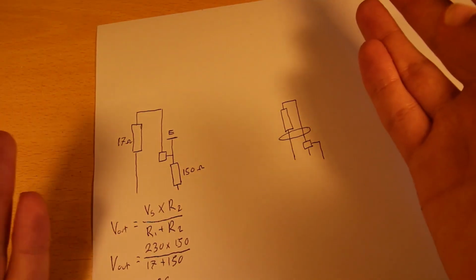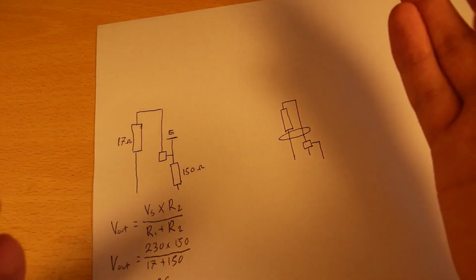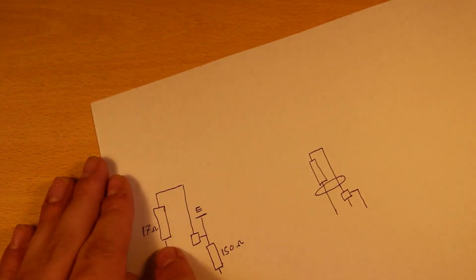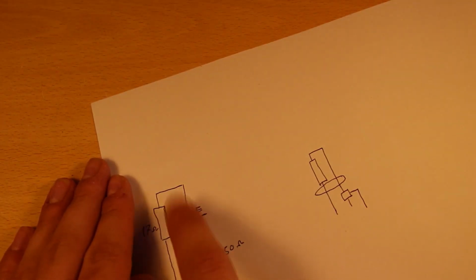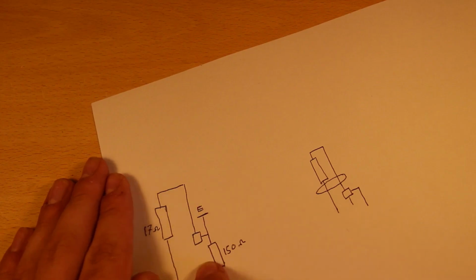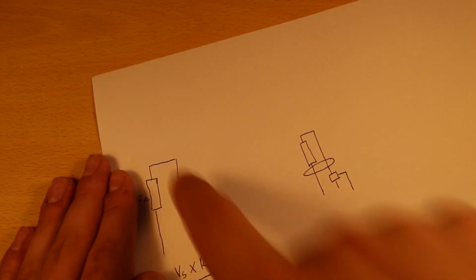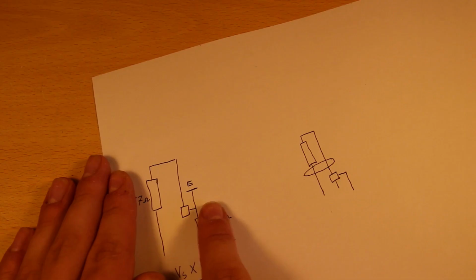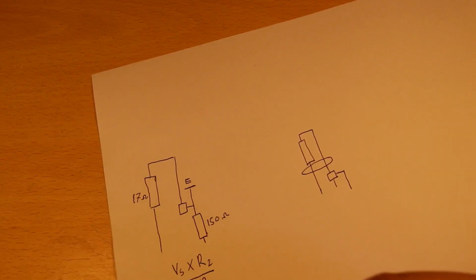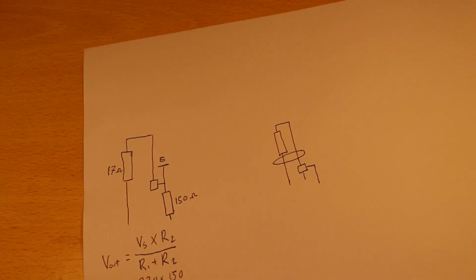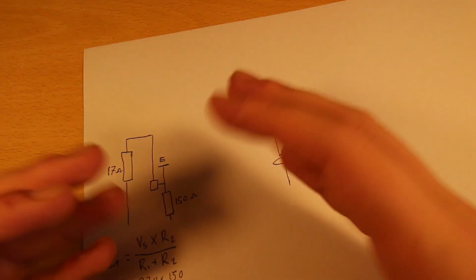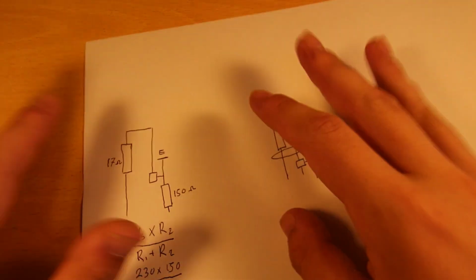Also, the earth rod will not make the RCD trip, because the RCD, as I said, will be measuring the imbalance between this conductor and this conductor. It does not care that the leakage is now happening after that, because the short to earth is after where the RCD is checking.